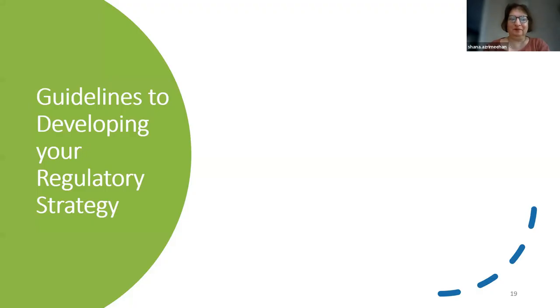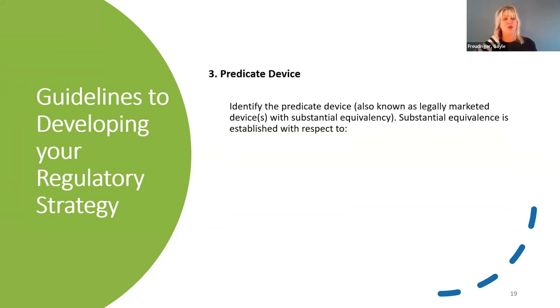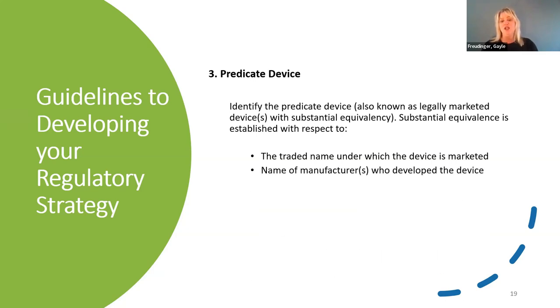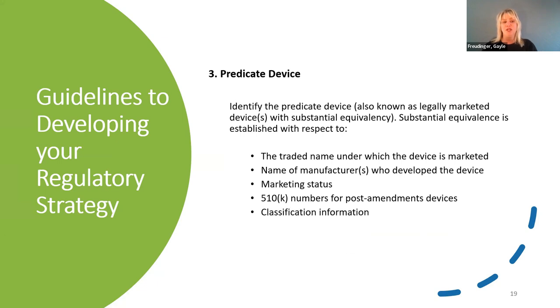Guidelines to developing a regulatory strategy also include a predicate device in most cases. After you've identified your product classification, the next step is to identify an appropriate predicate to which substantial equivalence can be established. In the 510K, for example, you're going to be comparing your existing device to a predicate. Information which can be used to find a predicate includes names: you look up names of similar devices and the trade name under which they're marketed. You could look up the manufacturer of the similar device, the marketing status, pre-amendments or post-amendments, 510K numbers for post-amendment devices, and then classification information. Most of this information on the classifications can be found on the FDA website.